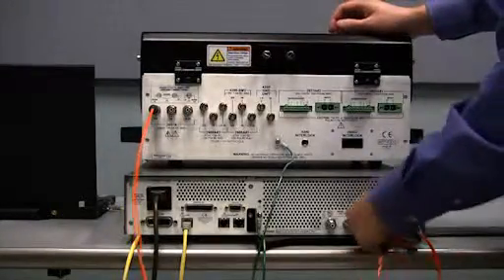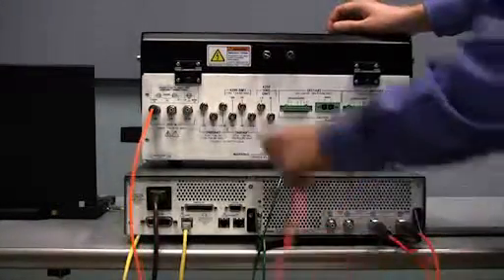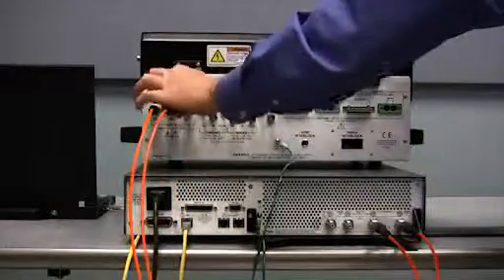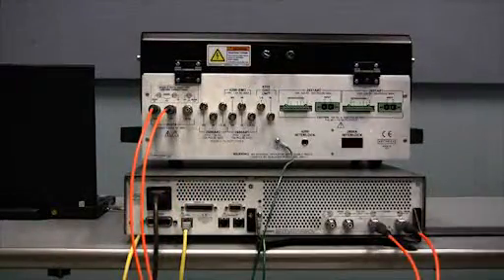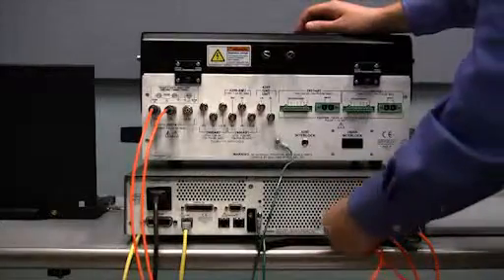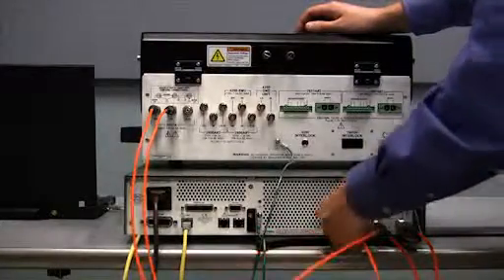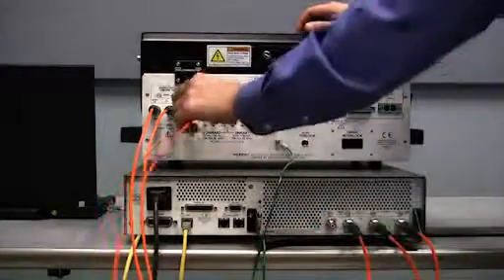However, for two wire local sensing only two cables are required. These cables also carry a guard signal to the fixture providing for pico amp level measurements even at 3000 volts.